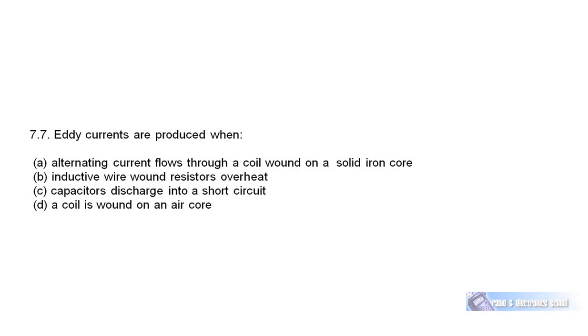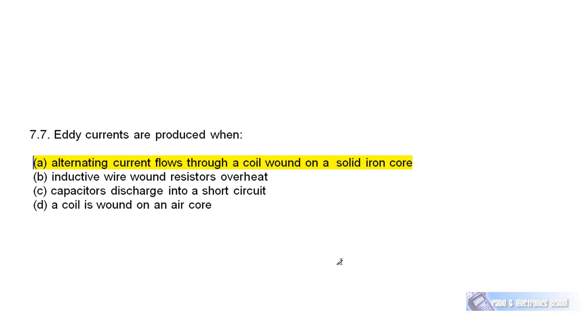Question 7.7: Eddy currents are produced when alternating current flows through a coil wound on solid iron. They're produced in the core material by the expanding and contracting magnetic fields around both the primary and the secondary. Eddy currents also flow in laminated iron but they're far less — laminated iron cores are far more efficient in terms of eddy current loss than solid iron cores.